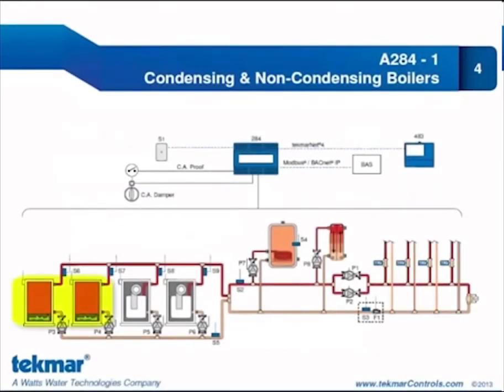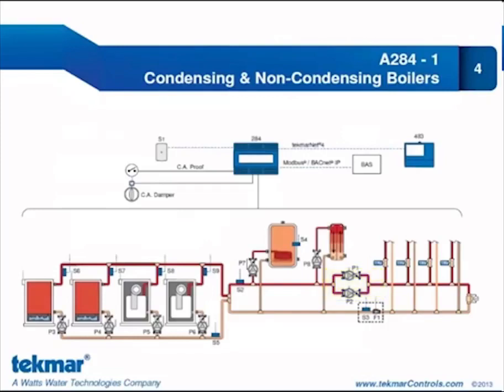In this first application, we have two single-stage non-condensing boilers and two modulating condensing boilers being operated to provide heat for indirect domestic hot water, a setpoint load, and space heating zones equipped with TRVs. You'll also notice dual primary pumps that can be sequenced for standby operation. We are doing primary pump sequencing and indirect domestic hot water simultaneously — in the 274 and 275 we had to choose one or the other, but now we can do both. That's another big advantage to the 284 boiler control.